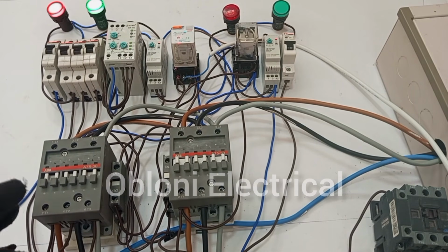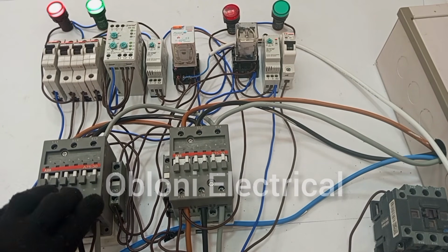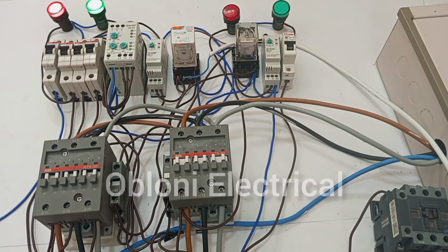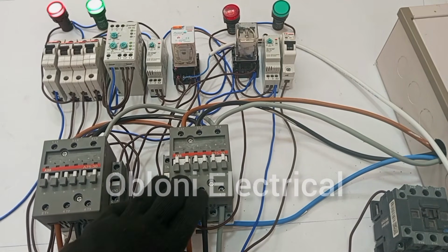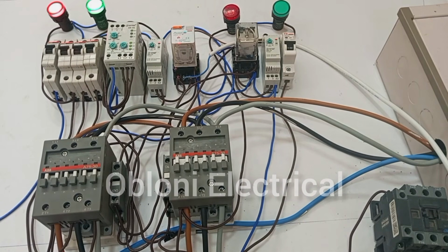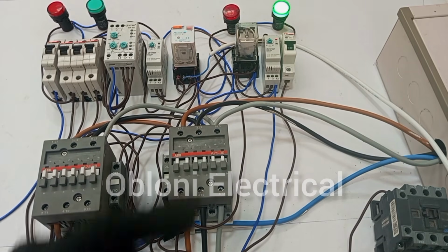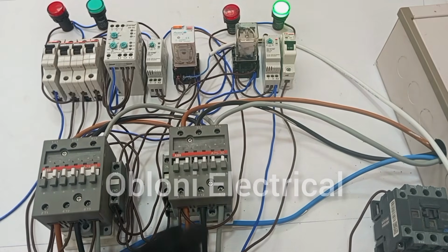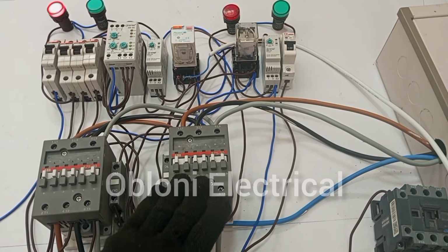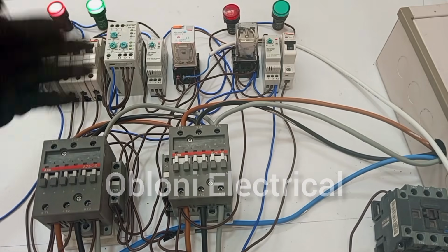Okay, so now main supply is working. So I'm going to turn off the supply to this contactor, which means that the main supply is off. And then immediately this one goes off. Because of the connection we have added now, this one will now turn on to supply power to the load. Okay. And then immediately you see that this one is now transferring power from the generator to the load. When the main supply is restored, the generator goes off and then the main supply takes over.